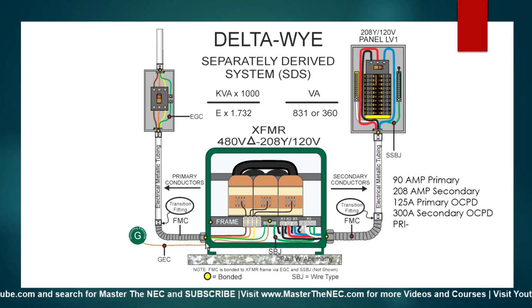So now let's deal with the bonding here and here. Okay, so this FMC is not being used as an equipment grounding conductor. One, because the circuit conductors it's protecting are larger than 20 amperes, and the fact that this FMC in our case is larger than 1.25 inches. So all those things mean you couldn't use this as an equipment grounding conductor. Well, that's the reason why we put a wire type equipment grounding conductor in it.